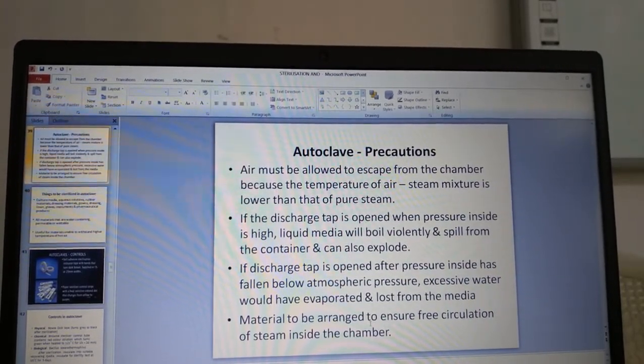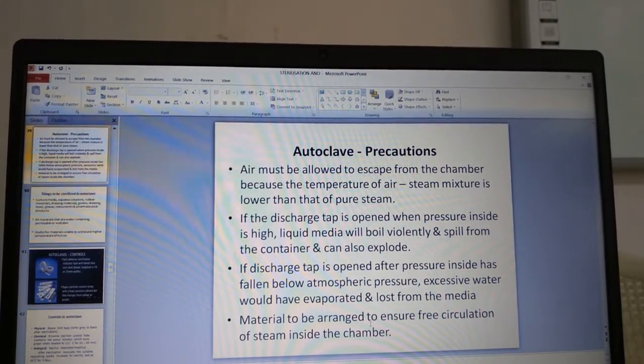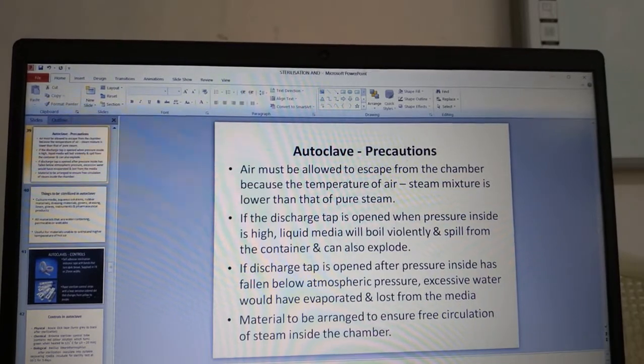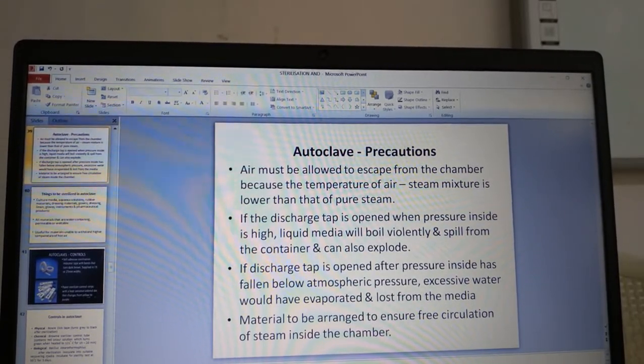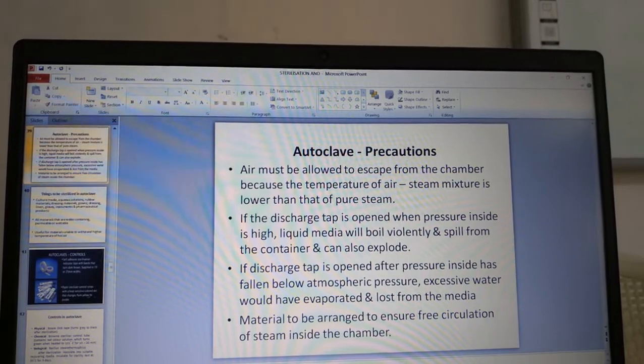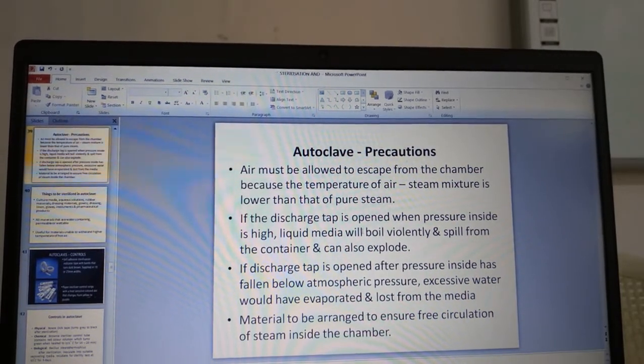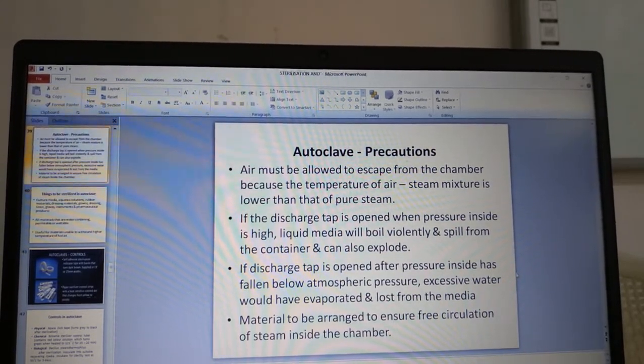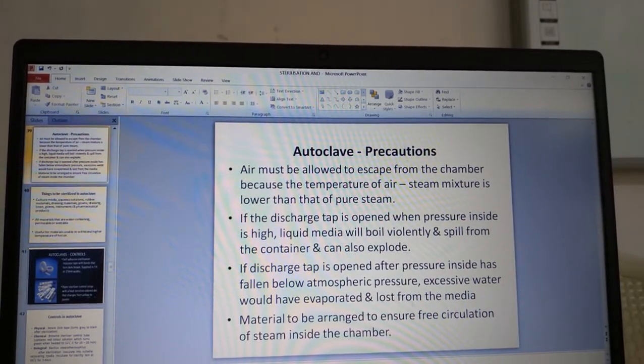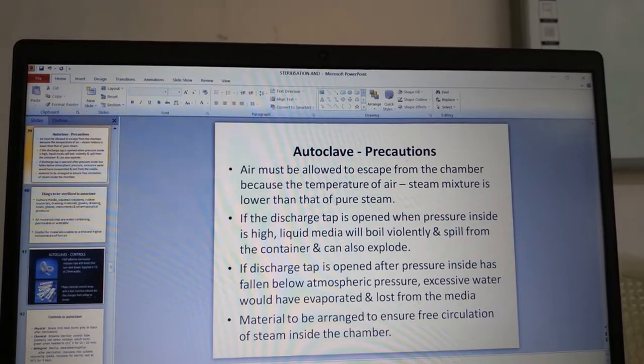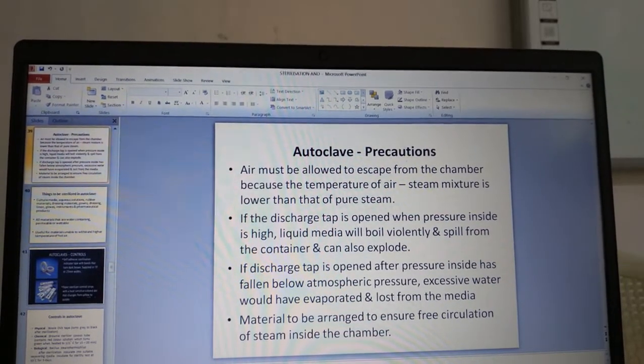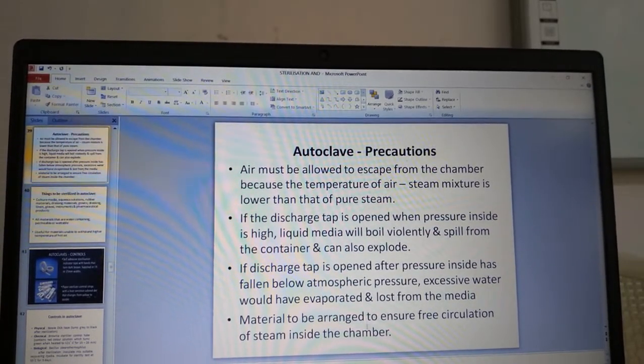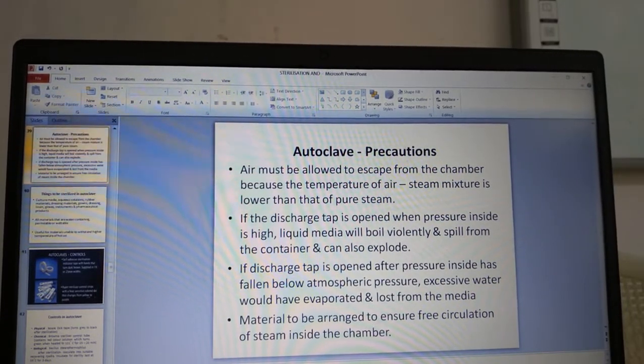Precautions for autoclave use: air must be allowed to escape from the chamber because the temperature of an air-steam mixture is lower than that of pure steam. If the discharge tap is opened when pressure inside is still high, liquid media will boil violently and can explode. If opened after pressure falls below atmospheric, excessive water would have evaporated from the media. Materials must be arranged to ensure free circulation of steam inside the chamber.